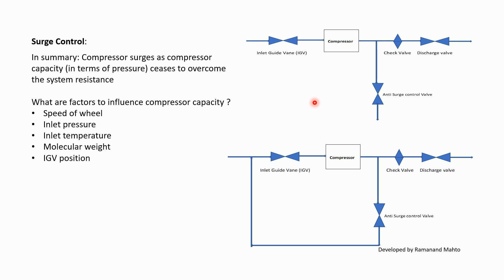There are two configurations. One is an air-operating compressor where suction is from atmosphere with an inlet guide vane (IGV), and an anti-surge control valve is connected venting to atmosphere. Downstream there is a check valve and discharge block valve. The other is a process compressor, which takes gas from the process with an inlet guide vane controlling the flow, and a recycle valve connected back to the suction side since it cannot vent to atmosphere. There is a check valve downstream and then a discharge valve going to the customer system.